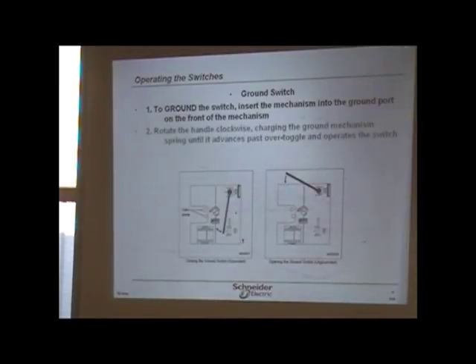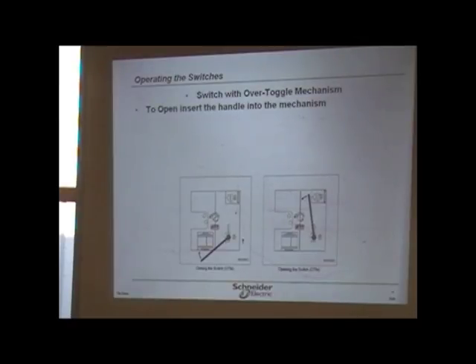This is the operator, and when I say operator, I'm talking about the operator arm. When you close the switch, notice the position where it's at. It's going to the grounded position. So what you're doing is you're taking it, and it shows you what you do. You go counterclockwise. Notice where the handle goes, up at the top, because you have one here at the bottom as well. I'm going to show you that in a minute. Switch with the over toggle mechanism.